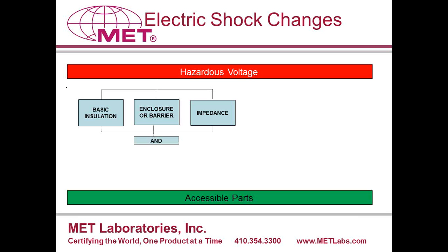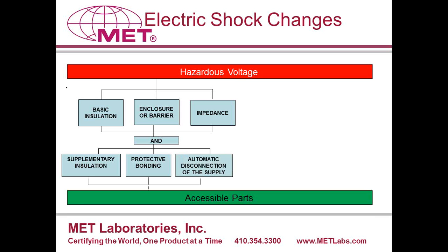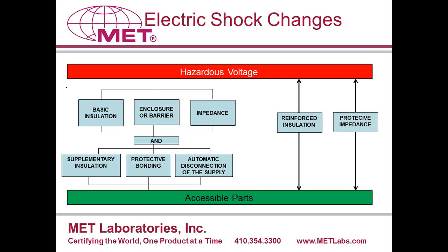Now, if one of those fails, you have to have an additional form of protection. The most common additional form of protection is metal enclosure and bonding. For plastic enclosures, it's supplementary insulation, which together with basic insulation forms double insulation. Another method is disconnection from the supply. Now, if you want, you can use one form of protection by itself, if it is either reinforced insulation, which would have twice the insulation as basic, or protective impedance that steps down the voltage and current and also provides insulation.